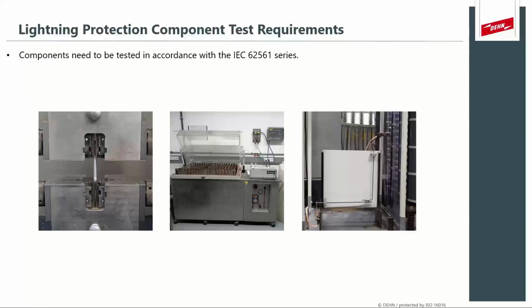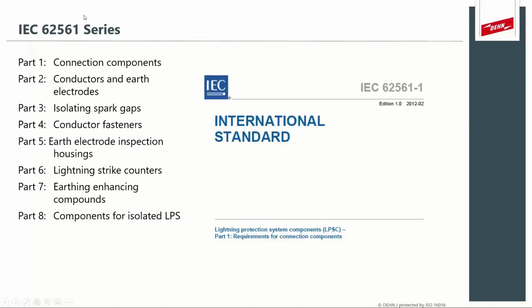So during the lightning protection or the lightning component testing, there's a lot of different tests involved that I will explain in more depth as well. So it's anything from force tests or torsion tests, and then tests against the atmosphere, salty air, sulfurous atmospheres, and things like that, and actual mechanical testing and electrical testing. What's important to note on this slide is that the testing standard that we use is known as the IEC 62561 series. It's been adopted by a lot of different countries all over the world, but the concept stays the same in most cases. Now, IEC 62561 is actually broken up into 8 parts. And for the purposes of this webinar, we will look at part 1, which is connection components, or the clamp, which you saw in this case.